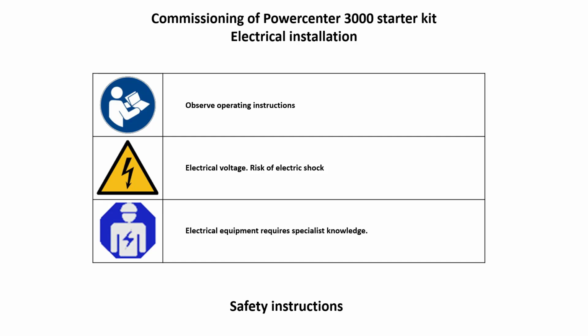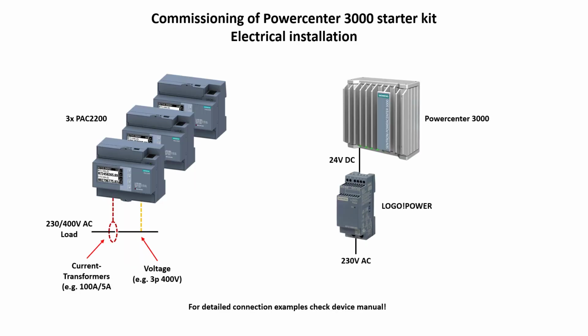in the device manuals. For installation of PAC2200 meters, additional current transformers are required, which are not included in the starter kit. These must fit the rated current of your application and be ordered separately. In addition to the current transformers, the voltage inputs of PAC2200 meters must be connected and are required for powering the device and voltage measurement. Powercenter 3000 requires 24-volt DC, where the local power supply is used.